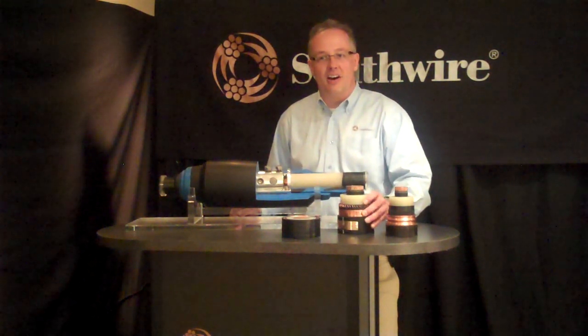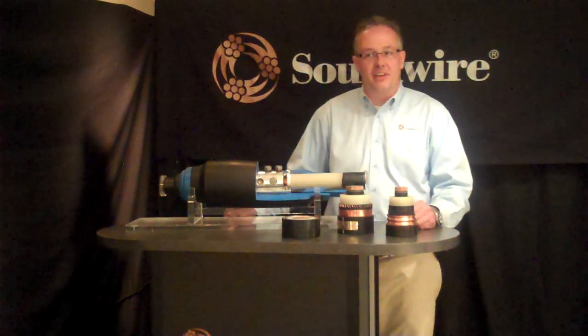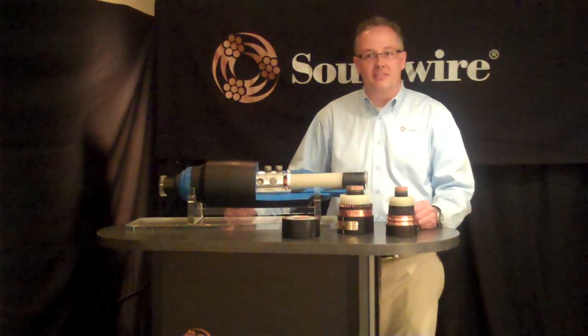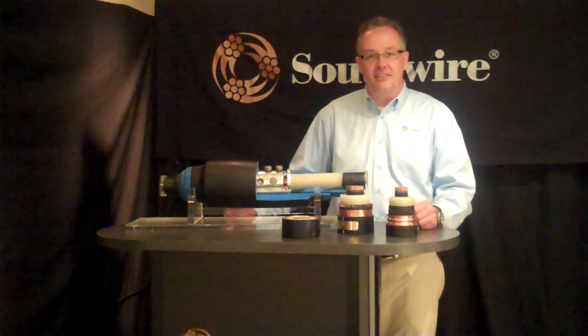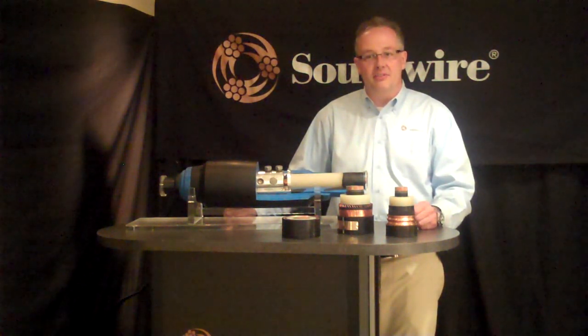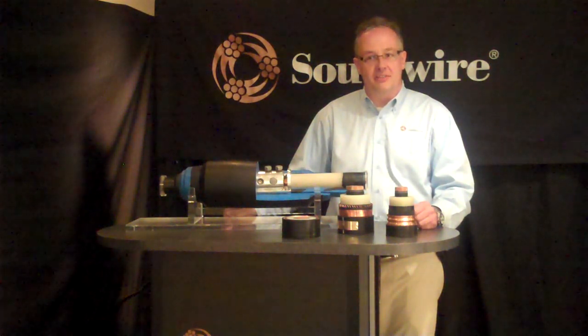The result are conductors with cross sections up to 4,000 kcmil, with 5,000 kcmil conductors yet to come. The result are increased ampacity, lower AC resistance, and lower losses for these cables.